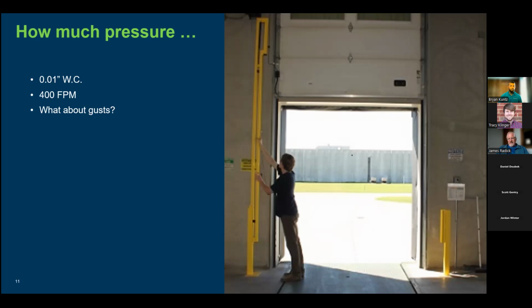That 400 feet per minute, if you were the gentleman standing there in the doorway and your building was pressurized to hundredths of an inch water column, you would stand there on a winter day and you would not feel air going past you. 400 feet per minute is very, very hard to perceive. It's very slow moving. So what you would stand in that door and perceive is not warm air rushing past you, but cold air not entering the building, which you typically see with any other type of heating system that's not pressurized. Okay.